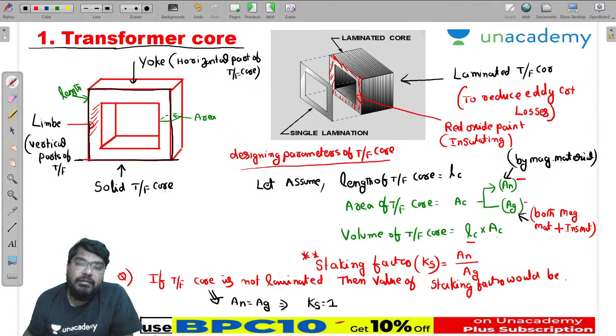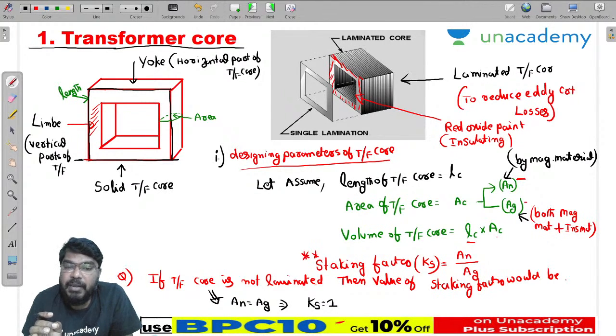So this is the first topic: designing parameters of the transformer core - meaning length, area, volume of the transformer core, and stacking factor. If the core is not laminated, the value of the stacking factor KS is equal to 1.